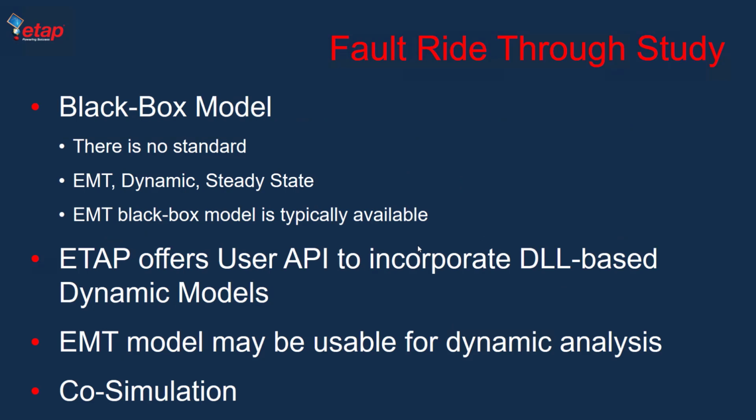Now, what is the solution? The solution is to use a black box model. The black box model basically means that the vendor provides the black box model with input output settings, and the simulation software tools communicate with that black box model. Let's say you feed the voltage, power, or currents, and then get the amount of current injected into the system.